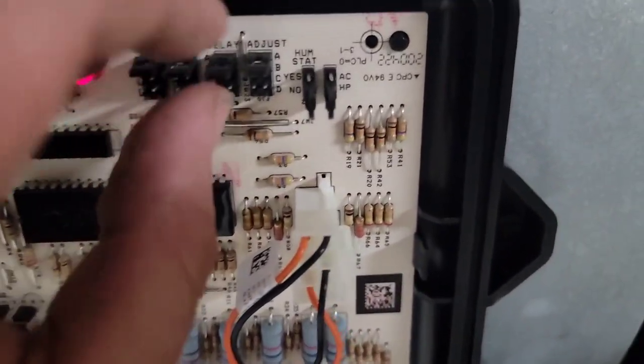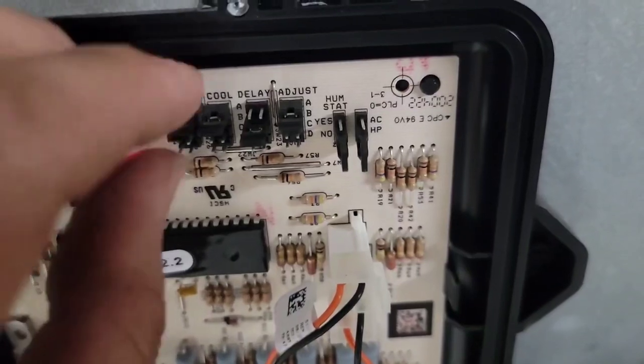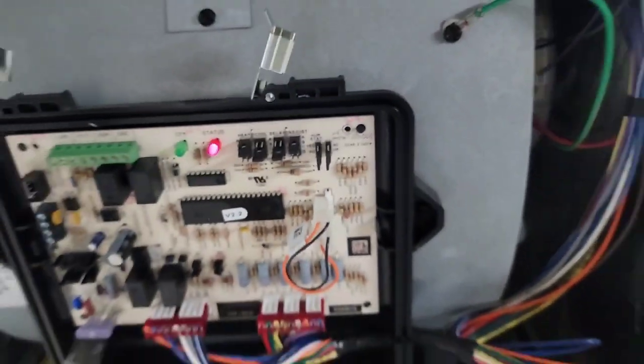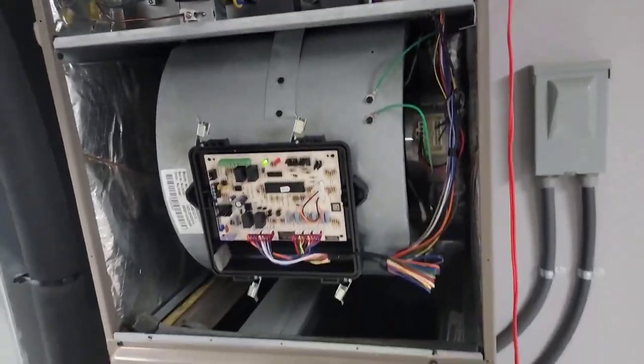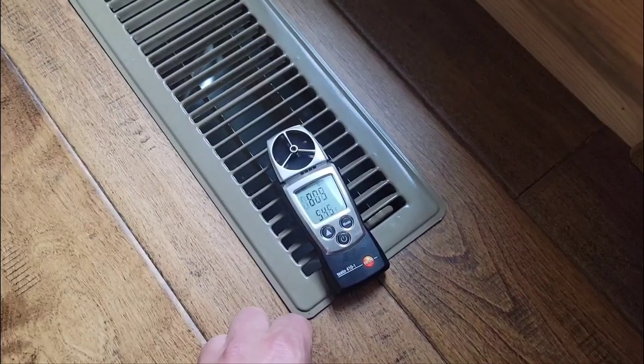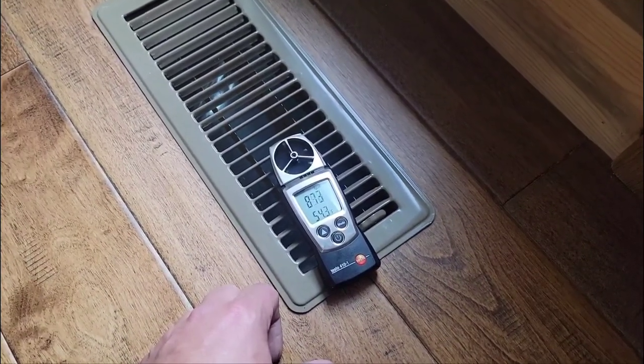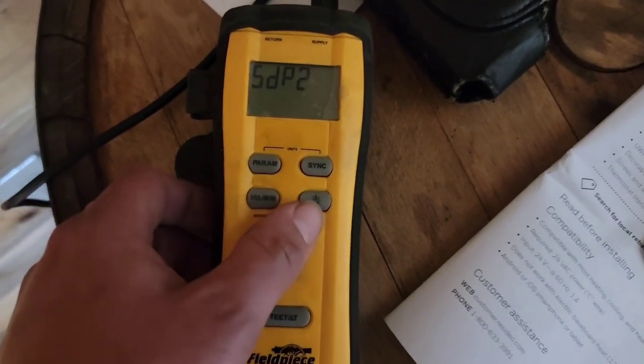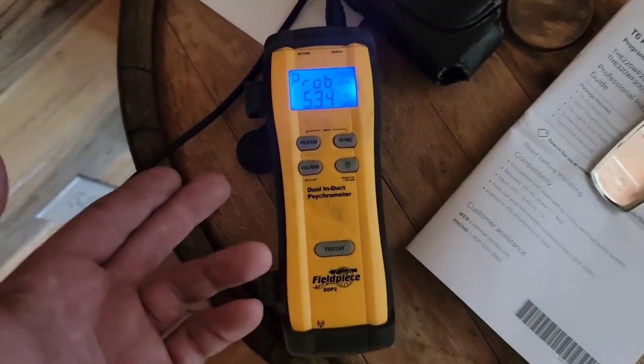We're going to put the delay tap on B, then go to the cooling tap and put it on B as well. Hear that? Fan speed just lowered. Now let's check the temperature split — it's still 71 in the house. Just turned on the dual in-duct psychrometer and it says 53 degrees. We just lowered the supply temperature by one degree.